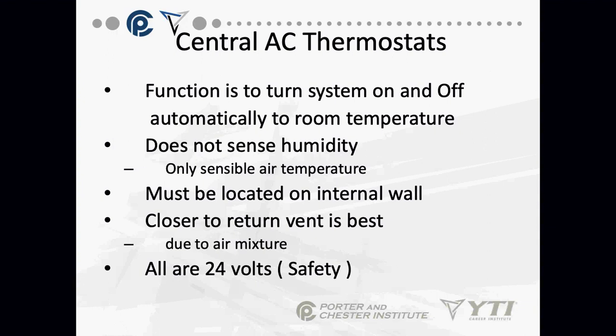Okay, thermostats don't sense humidity when we're talking about a plain thermostat. Okay, some of our digital thermostats might have humidity sensors also built into them, but a basic thermostat senses only sensible air temperature. That's temperature I can measure. Okay, thermostats need to be located on an internal wall. We want to locate them closer to return air vents because that's pulling the room air into it. Okay, it's where we get our best readings.